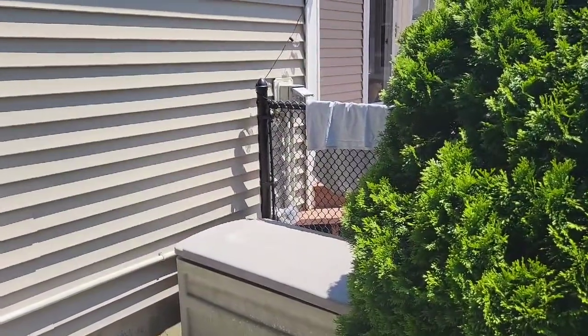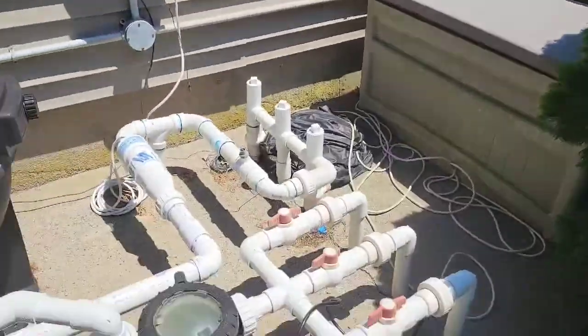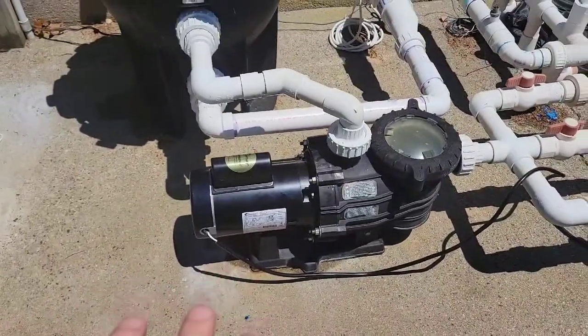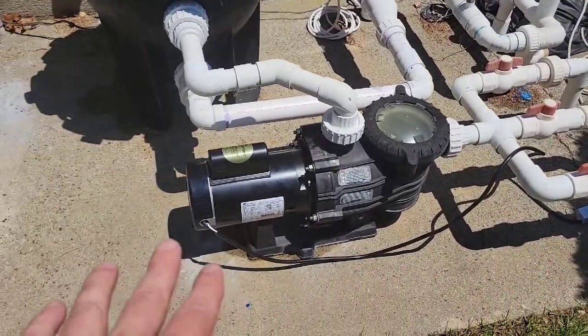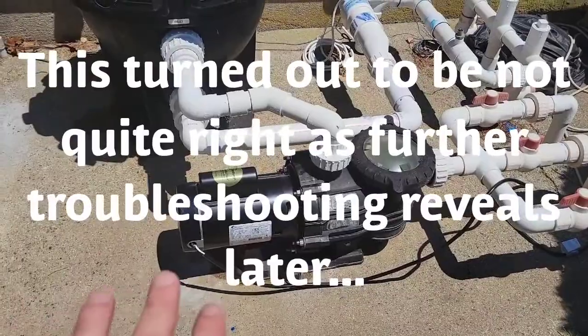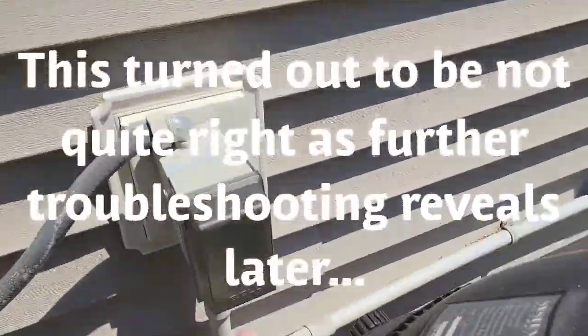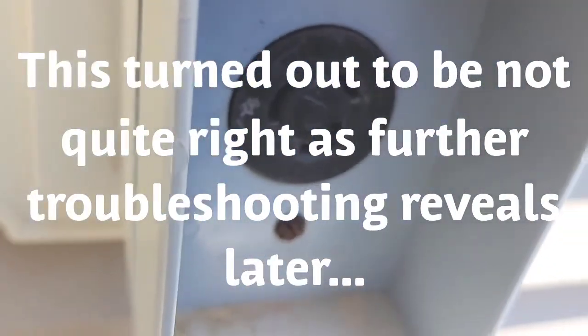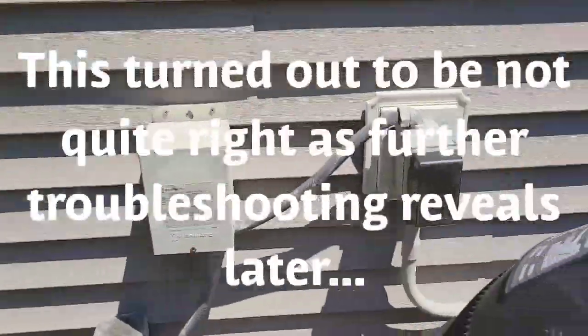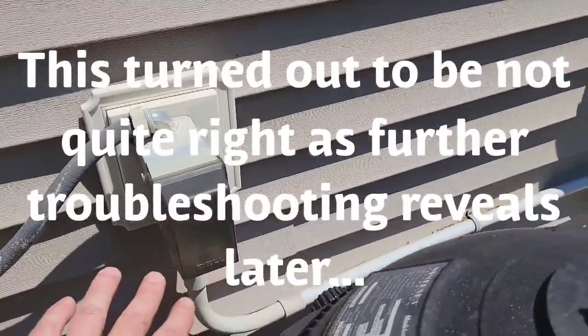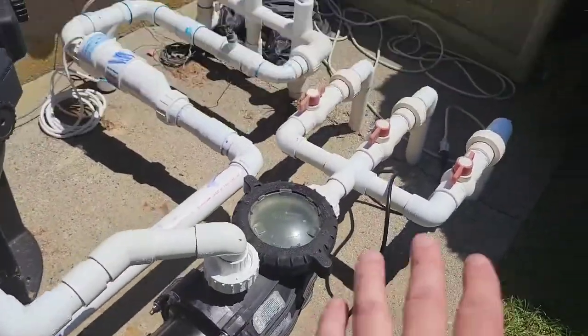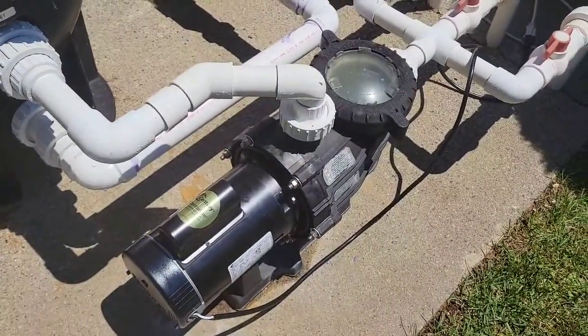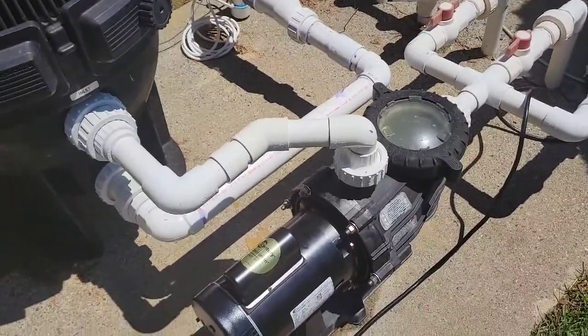So while Joe takes apart the switch box so we can access the wiring, I just want to touch on something real quick. The new motor that Joe temporarily wired has a switch in it for 230 or 115, and originally he was thinking this was 230 because it's got a strange looking three-prong. Where's the old cable, Joe? It's in the garage. All right. Anyway, he had just assumed this was 230, but as we went through it yesterday, we realized everything's 115. And when he temporarily rigged this to the receptacle, he did switch it to 115. So we now know it should be a 115 motor.